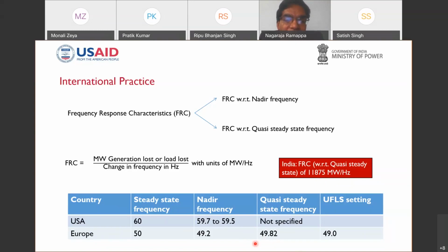Now coming to the practices in the USA, being a 60 Hz system, the nadir frequency is 59.7 to 59.5. Quasi-steady state frequency, at least we were not able to get an authenticated reference for that. But when it comes to Europe, a 50 Hz system, the nadir frequency is 49.2 and the quasi-steady state frequency is 49.82, and the under frequency load shedding in Europe is happening at 49 Hz. Therefore, before UFLS reaches 49 Hz for the major loss of a generation, within the limit of the largest unit size, we should not allow the frequency to go below 49.2 Hz in the European practice. Next, please.